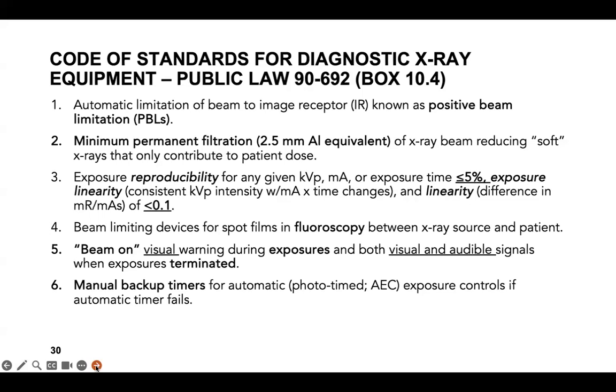So the Code of Standards for Diagnostic X-ray that was set forth by Public Law 90-692, and if I'm not mistaken, this table is in your book. This slide also would be a good reference to study for the registry. So knowing the automatic limitation of a beam to image receptor, which is the positive beam limitation, PBL, the minimum permanent filtration, which is 2.5 millimeters of aluminum equivalent in the X-ray beam, reducing soft X-rays that only contribute to patient dose. So that filtration cleans up those low energy X-rays that are not beneficial.